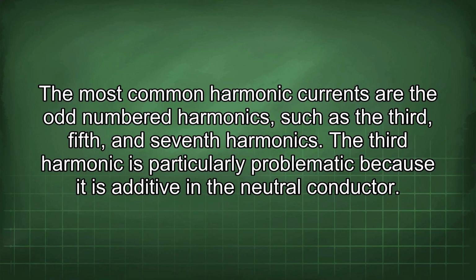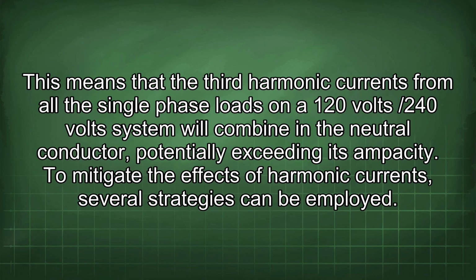The third harmonic is particularly problematic because it is additive in the neutral conductor. This means that the third harmonic currents from all the single-phase loads on a 120-volt/240-volt system will combine in the neutral conductor, potentially exceeding its ampacity.